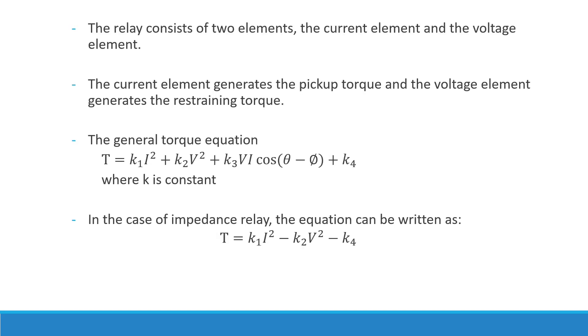In the case of an electromechanical relay, the relay consists of two elements: the current element and the voltage element. The current element generates the pickup torque and the voltage element provides the restraining torque. The general torque equation is given by T = K1·I² + K2·V² + K3·V·I·cos(θ − φ) + K4, where K1, K2, K3, and K4 are constants. In the case of an impedance relay, the equation becomes T = K1·I² − K2·V² − K4.